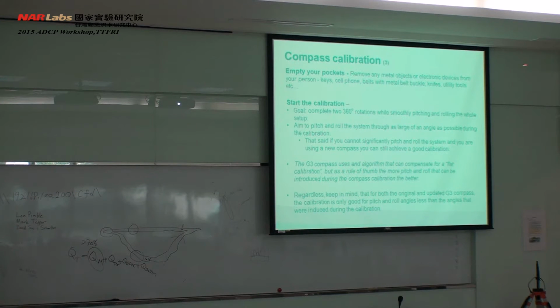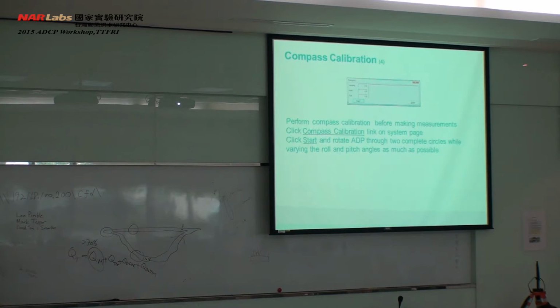And remember that the calibration is only good for the pitch and roll to which we've calibrated it. So if we've done a flat calibration and we've got very little pitch and roll, you really want to be making sure that you don't have any pitch and roll while we're doing our discharge measurements.